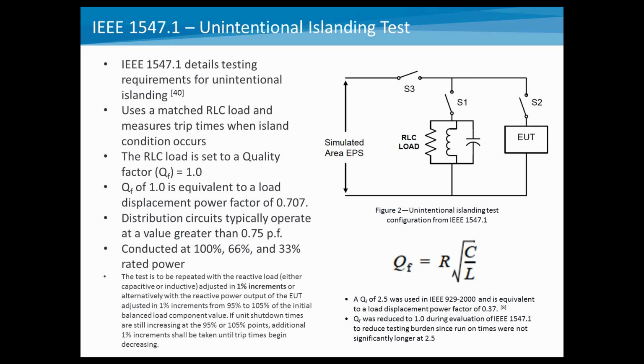In this case, it's an RLC load that basically matches real and reactive power. And to conduct the test, you match the RLC load bank with the output of the device under test until you have basically no current flowing through that switch S3. At that particular point, you can open that switch and see how long you can maintain that island between the load bank and the equipment under test. A couple things to realize on this is that you do have what is considered the worst condition that you can create to understand how well the anti-islanding techniques work. So this RLC load is very exactly matched to the output of the unit under test.